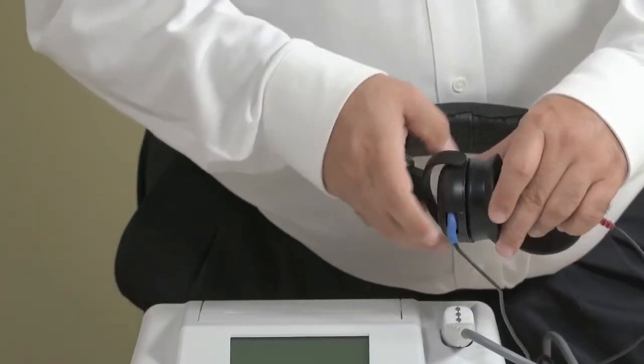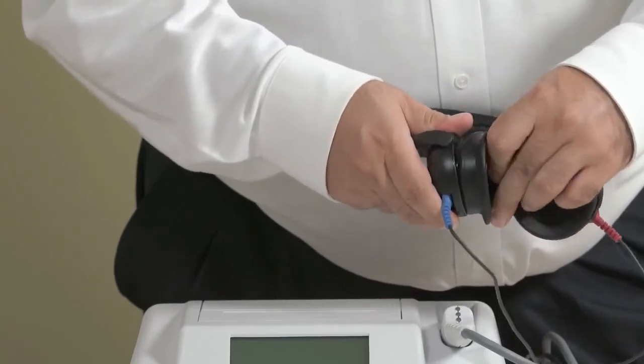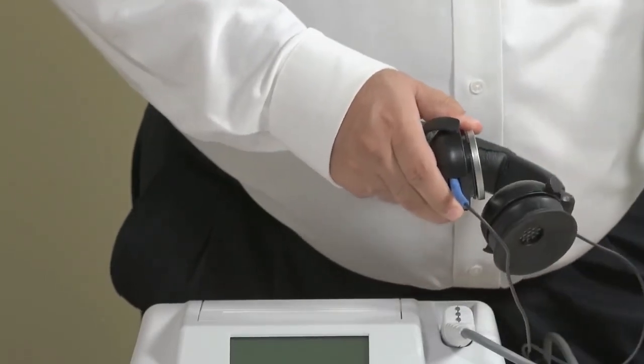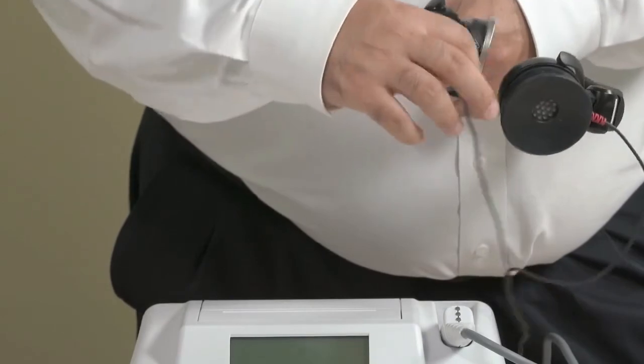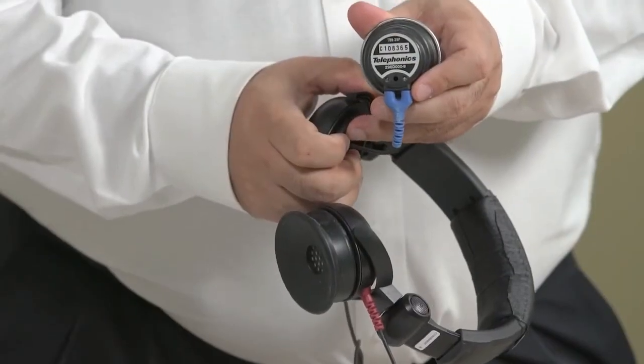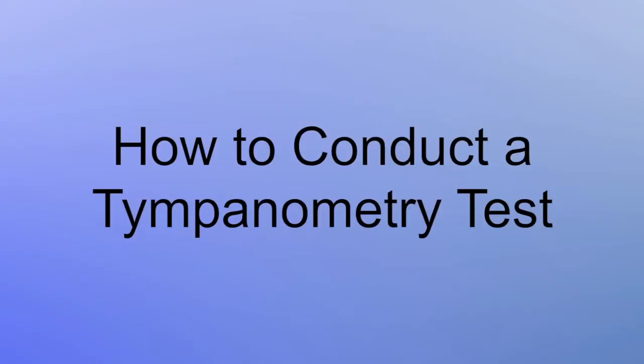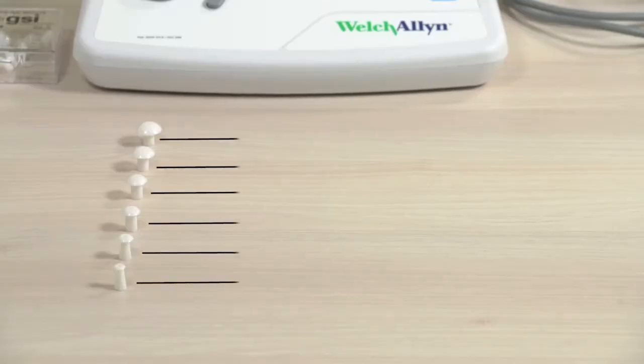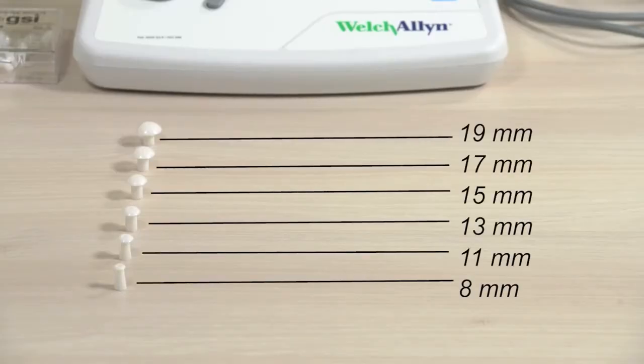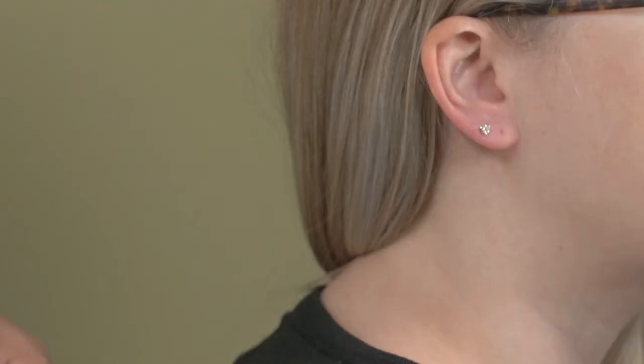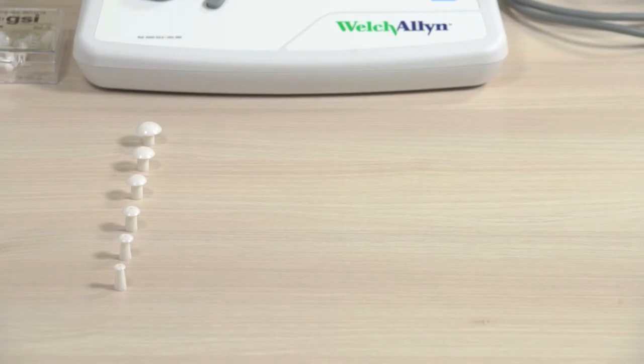If you experience an issue with sound in either side of the headphones, it is possible to determine the source of the problem by switching the red and blue Y cords. Now we'll show you how to conduct a tympanometry test. Here is a selection of ear tips. Six different size ear tips are provided with this instrument. You should inspect the ear canal opening to make sure there is no blockage or drainage, and this will also help you select the right size tip for your patient.